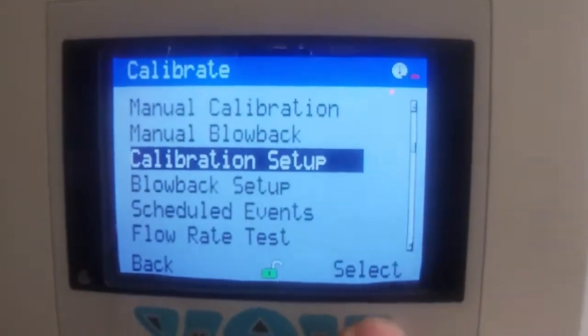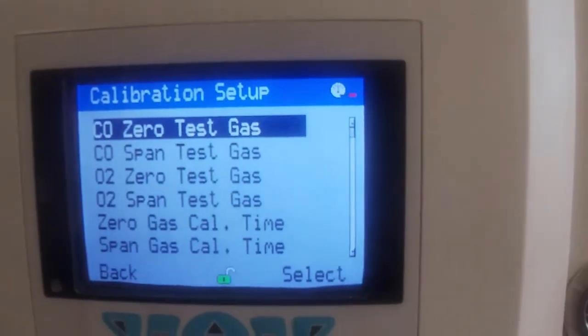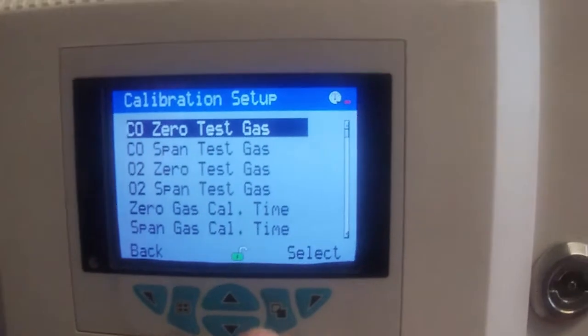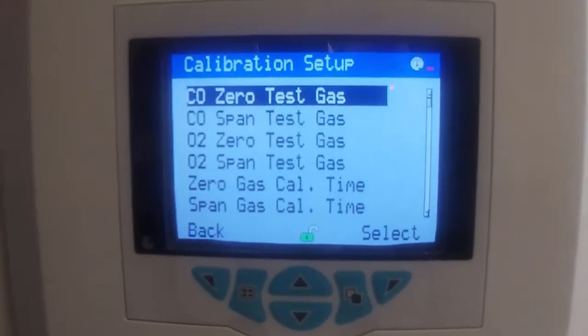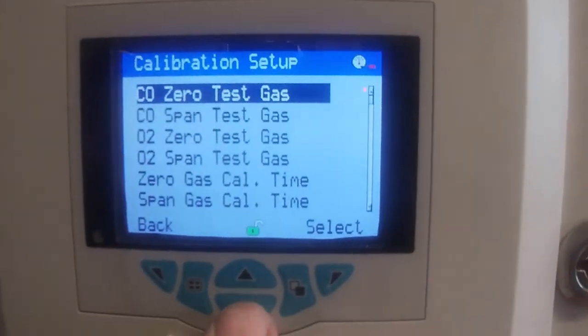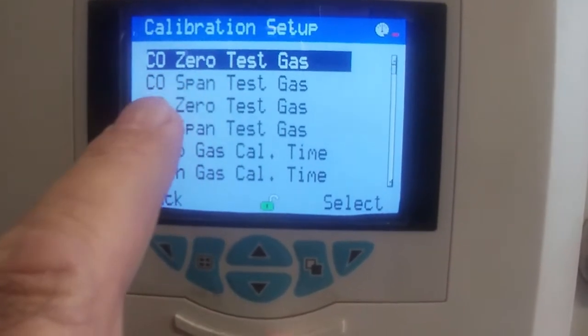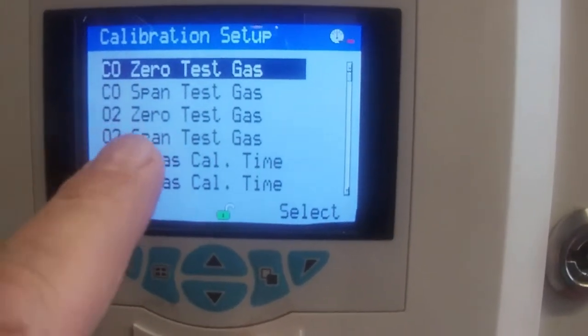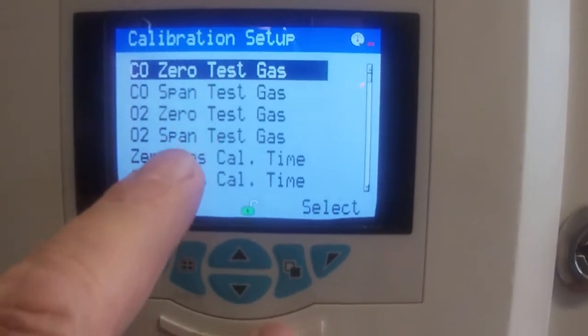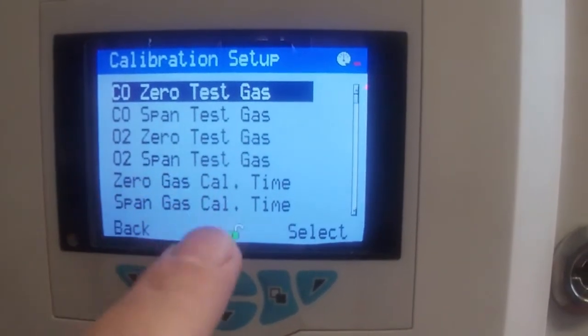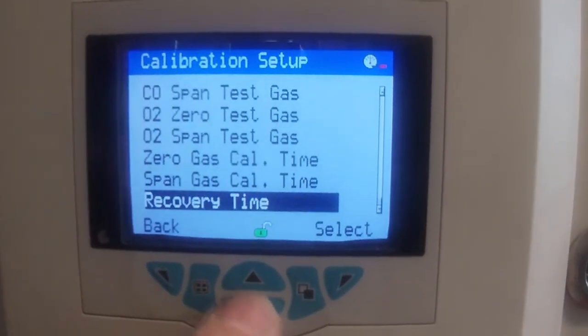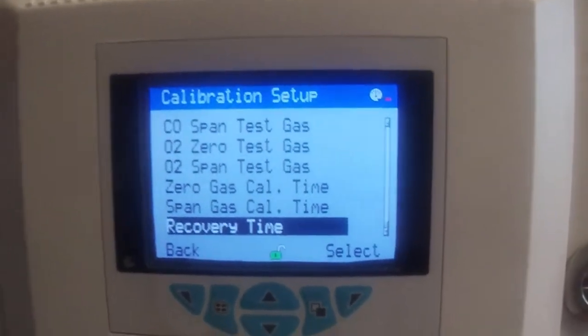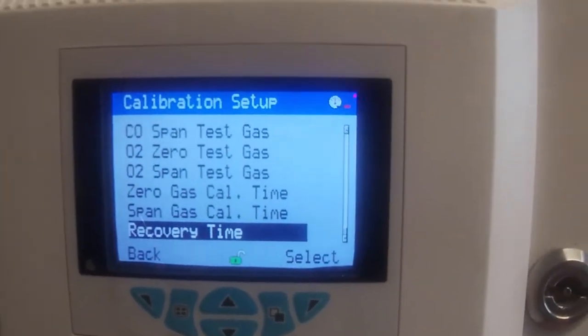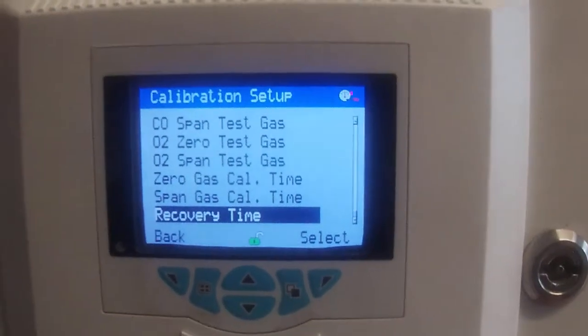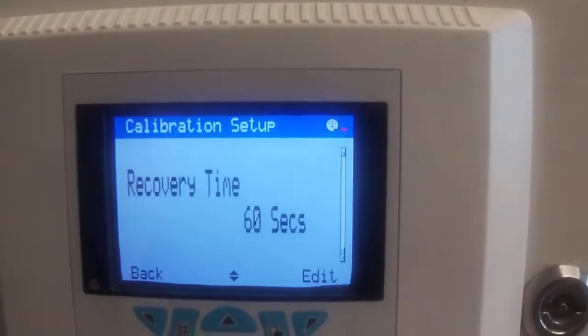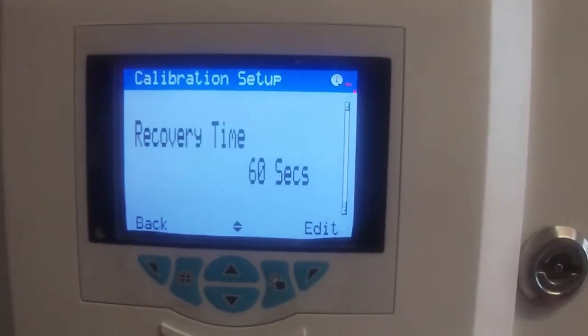Then there's a calibration setup in here, which is going to allow me to tell it what zero gas, span gas, etc. it's got, and how long these things are going to run. How many minutes do you want? And typically it's 5 minutes. The default is 5 minutes, and I left it set at those values. So zero gas content for CO gas, span gas, and same thing with zero gas calibration time. And if I keep going down, there's a recovery time. How long between gases do you want to wait until it's stabilized? And we typically set that for 5 minutes. And I think if I was to select it, you would see, well, I got it, I'm sorry, 1 minute, 60 seconds. It's set for 60 seconds.